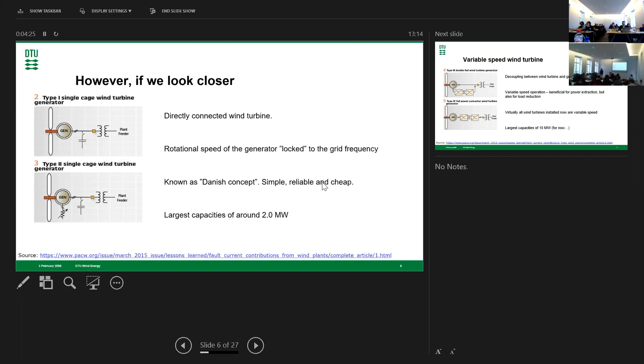Then we moved to variable speed wind turbines, where between the generator and the grid you start having more equipment, which is the power electronics. First were double-fed wind turbine generators, because the generator had a double connection to the grid: one directly, the stator, and the rotor connected through power electronics. Today it's the full-scale, full power converter, where the whole transfer of power from the mechanical to the electrical side is done through the power electronics. This has basically allowed decoupling of the mechanical part of the wind turbine from the grid, enabling variable speed operation.